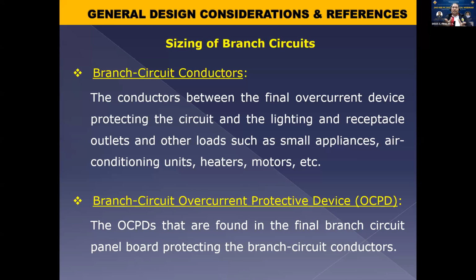Then it's your due diligence to do your validation. That's why I put in here the provisions, para ma-check nyo rin kung accurate ba yung nailagay ko dito na provisions. Okay? So for sizing of branch circuit conductors, these are the conductors between the final overcurrent device, or the branch circuit panel board, and a certain device, either lighting or outlets or other loads, to the equipment itself.